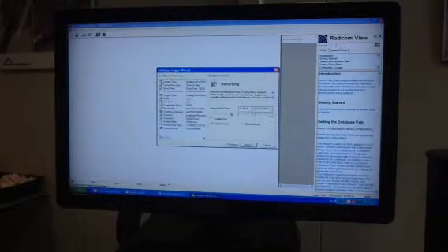Recording. Once you've done the process of putting all the parameters in the logger, as long as the record start time is in the past, the logger will start recording straight away. If obviously the time and date is in the future, it won't start recording until it has reached the time and date on this screen.